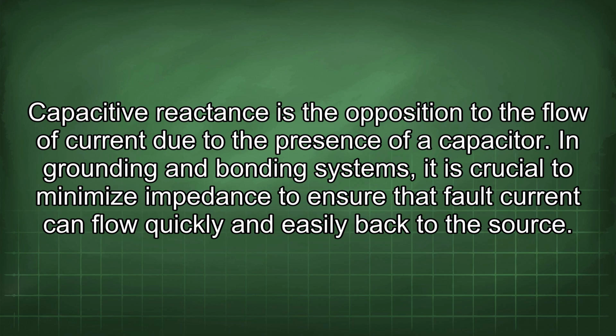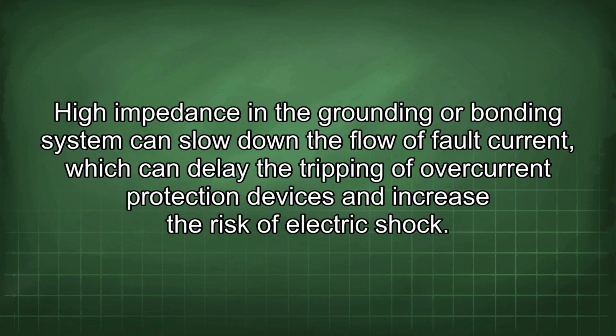In grounding and bonding systems, it is crucial to minimize impedance to ensure that fault current can flow quickly and easily back to the source. High impedance in the grounding or bonding system can slow down the flow of fault current, which can delay the tripping of overcurrent protection devices and increase the risk of electric shock.